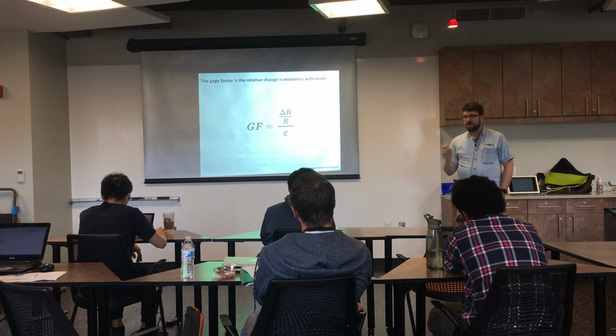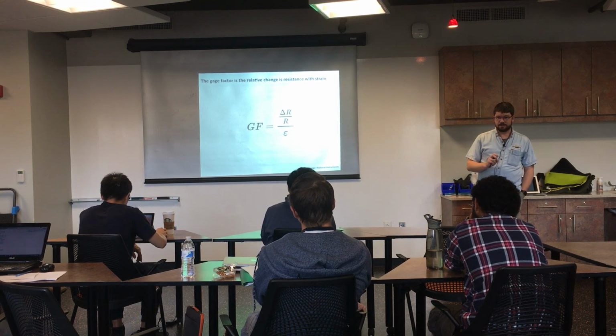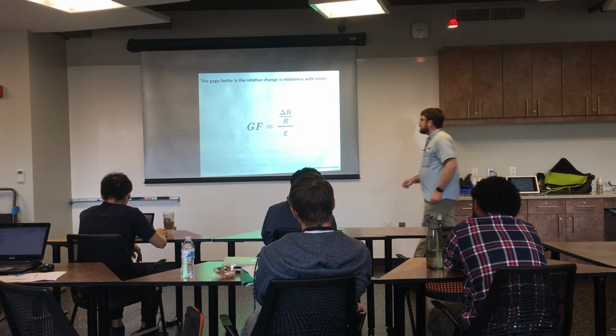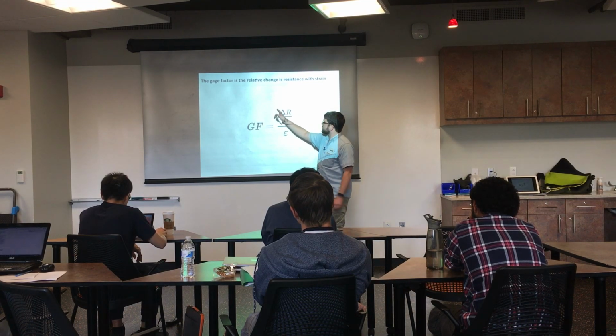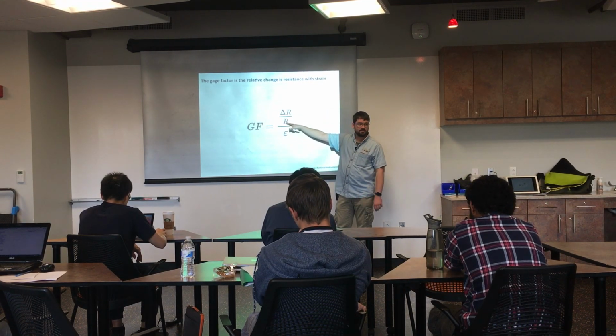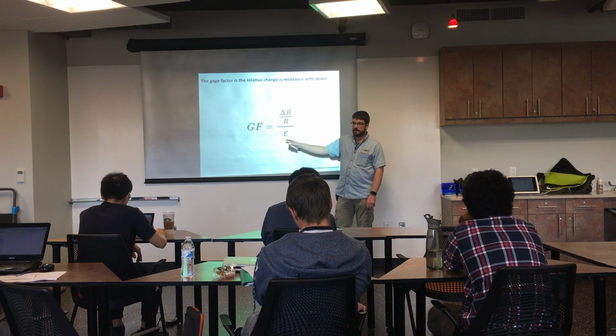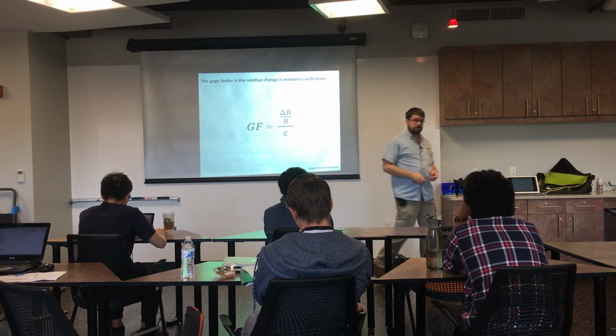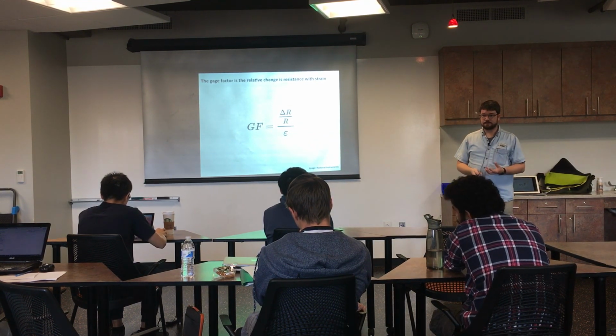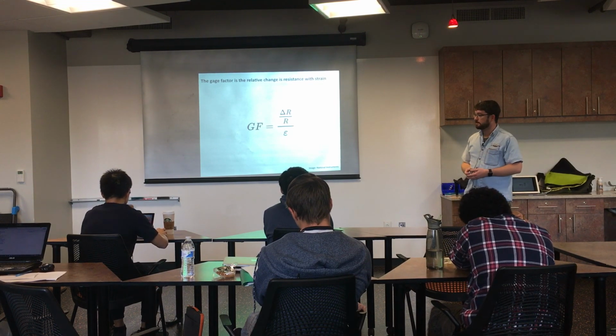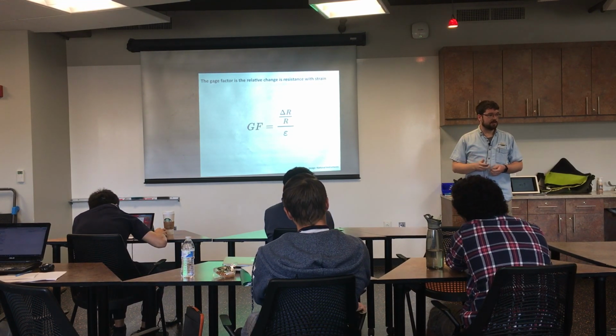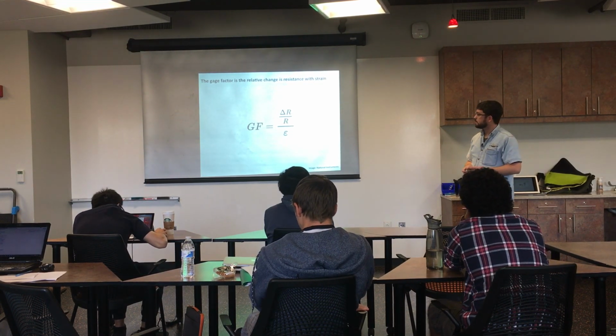Every strain gauge has a gauge factor on its package. The gauge factor is the relative change in resistance, delta R over the at-rest resistance, divided by strain. It tells you how sensitive the strain gauge is, and it plugs into all the formulas we use to calculate strain.